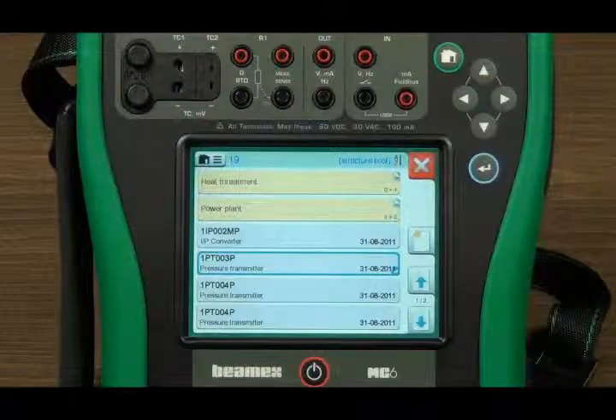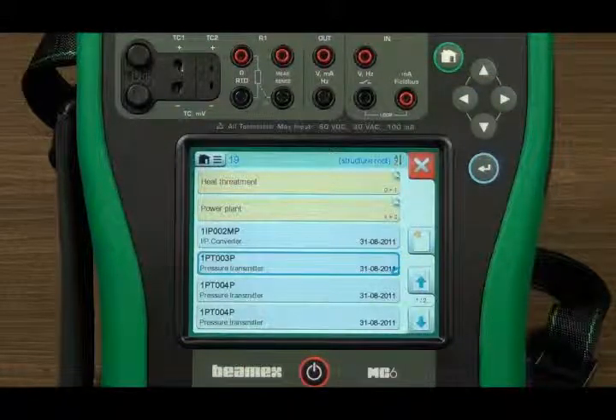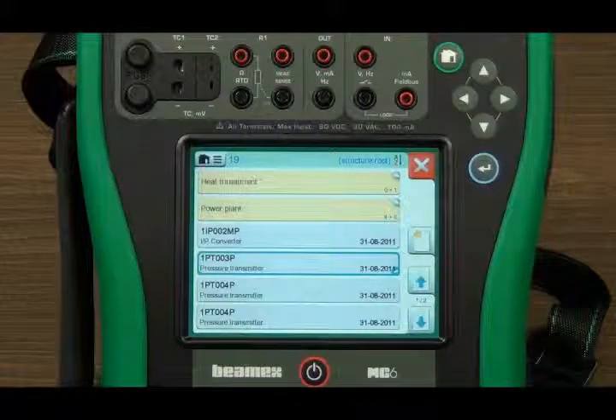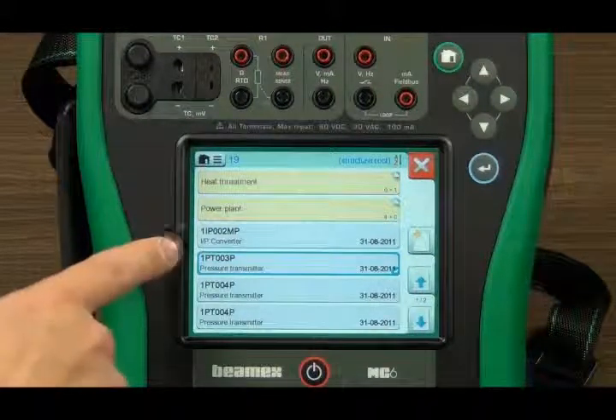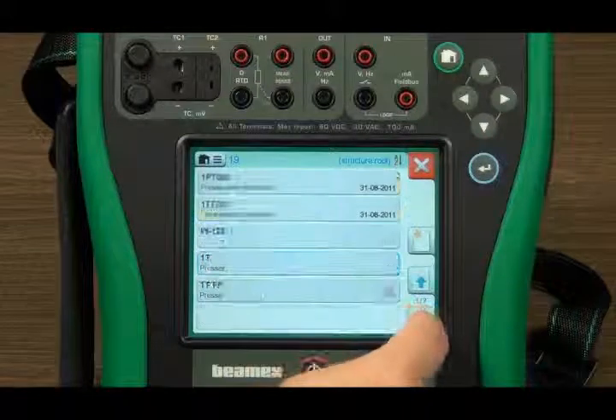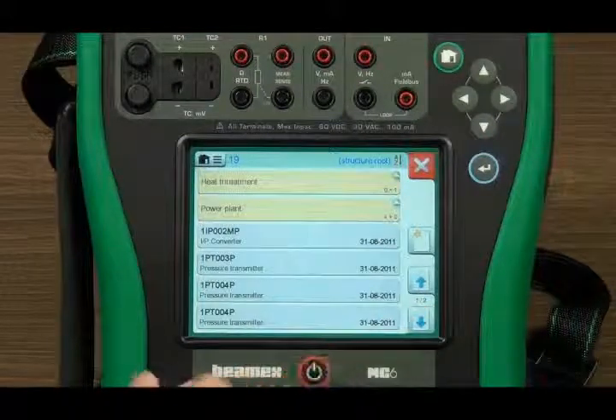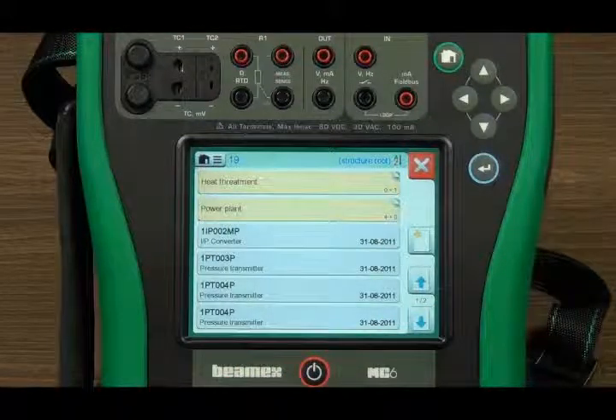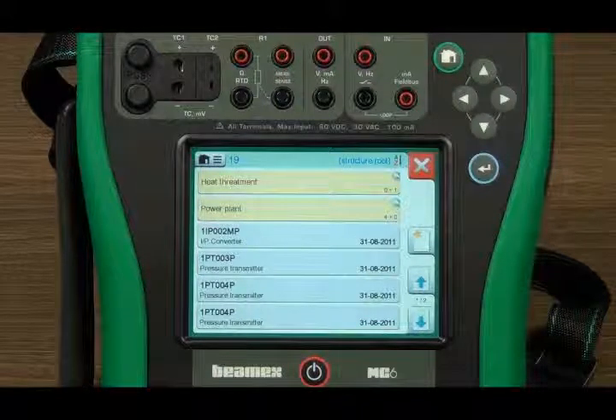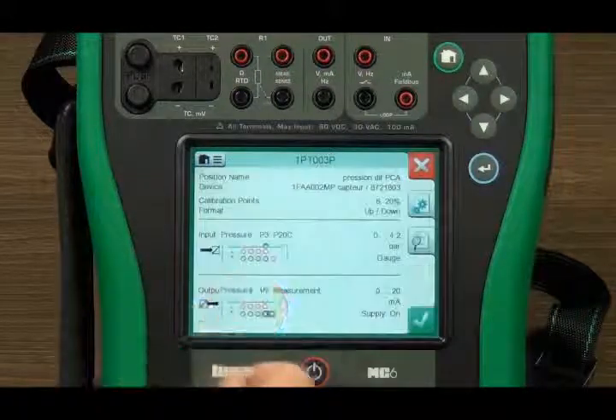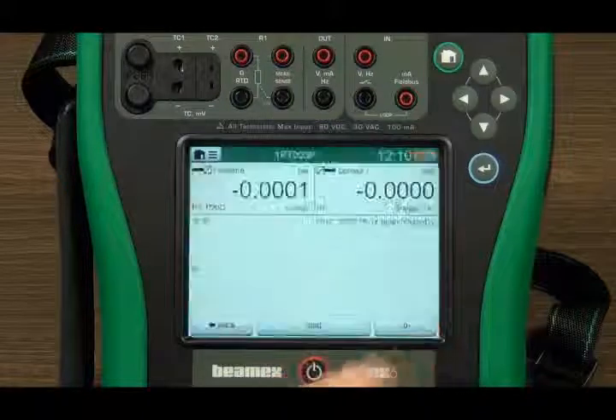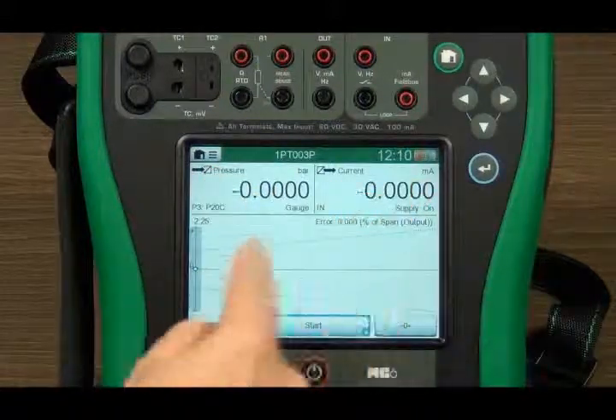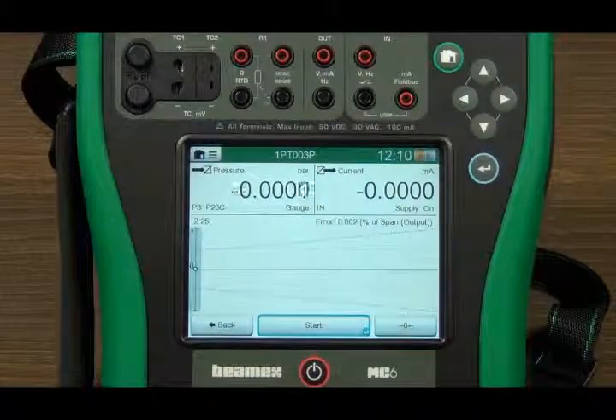Documenting calibrator. The purpose of the documenting calibrator is to calibrate process instruments and to document calibration results. First, you will see a list of the instruments currently in the memory. These are sent from calibration software or created in the calibrator. From here, you can select the instrument you want to calibrate by touching it. The actual calibration screen will show the instrument input, output and a large error graphic area. Now, you can connect your instrument and do the calibration.